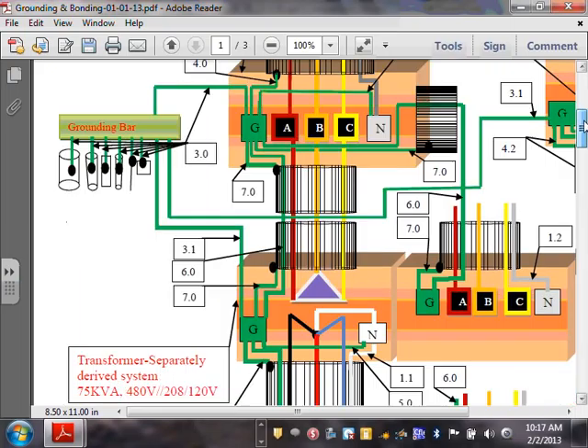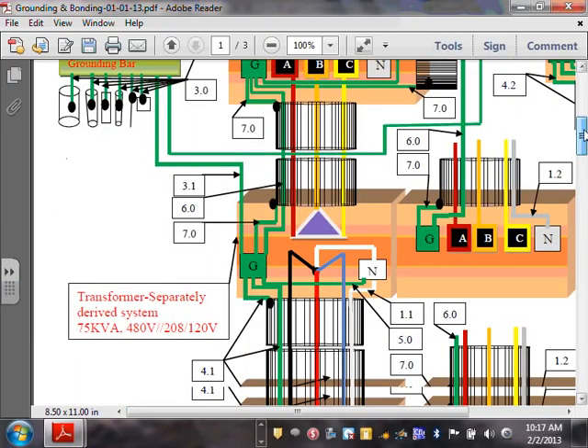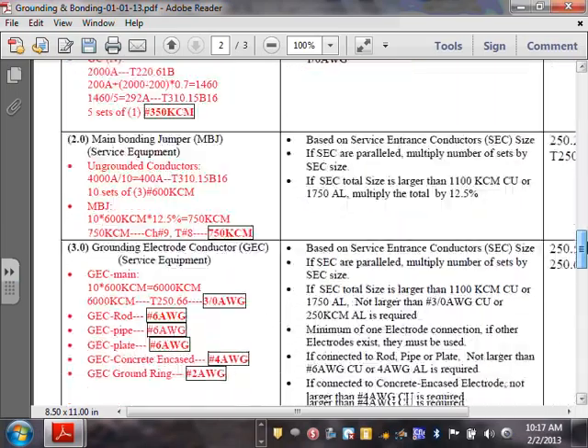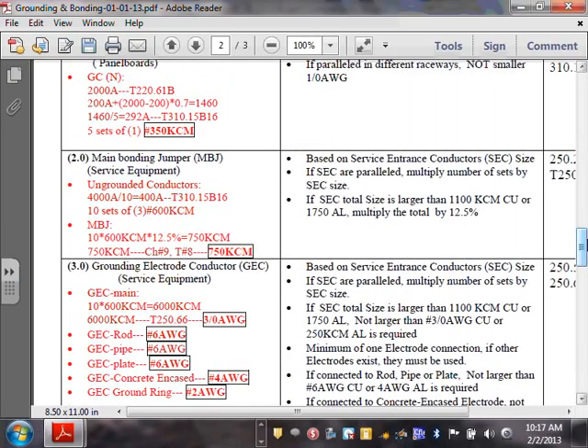Let's go all the way up to main bonding jumper, which was number 2. Can you guys see that? Number 2 at the top. Okay, let's go to number 2. Here's number 2, main bonding jumper. Here's how we size the main bonding jumper, guys. That's when you bond your neutral. I have a 4,000 amp switchgear. I single-handedly, Chad, decided to pull 10 runs. You can do 12 or 11. So 10 runs, divide by 10, gets you 400, go to 310.15(B)(16).